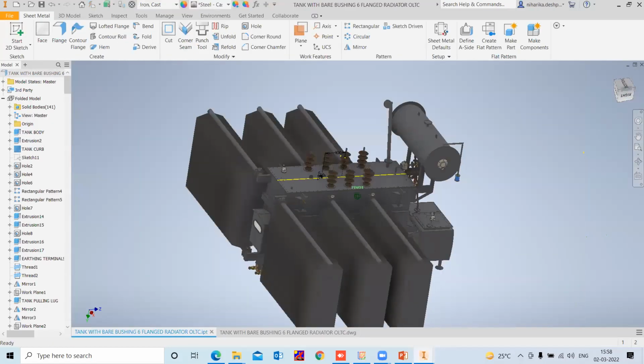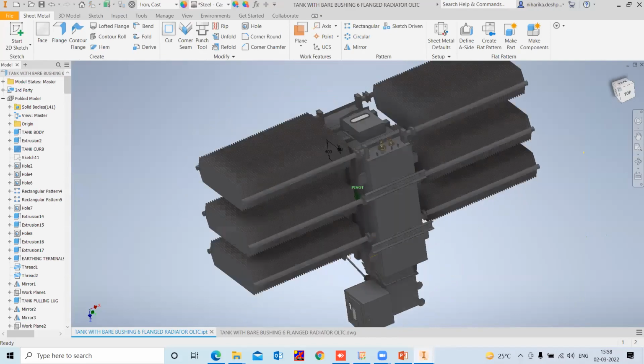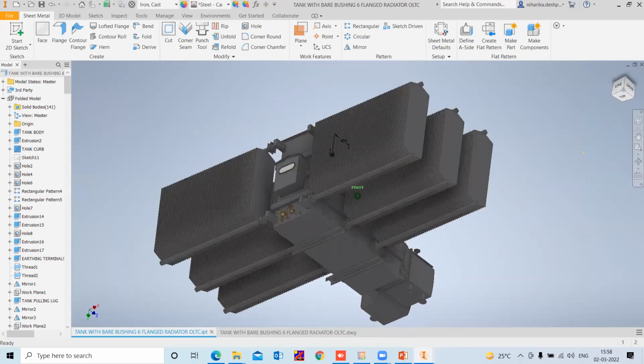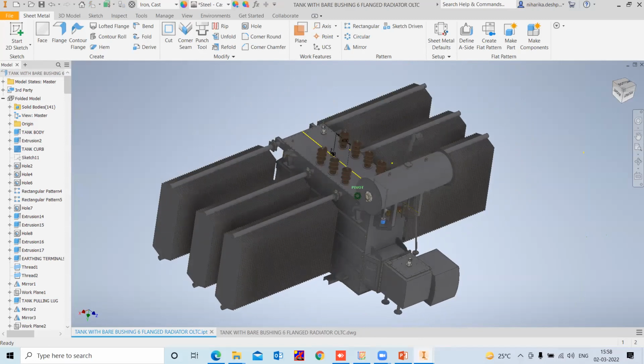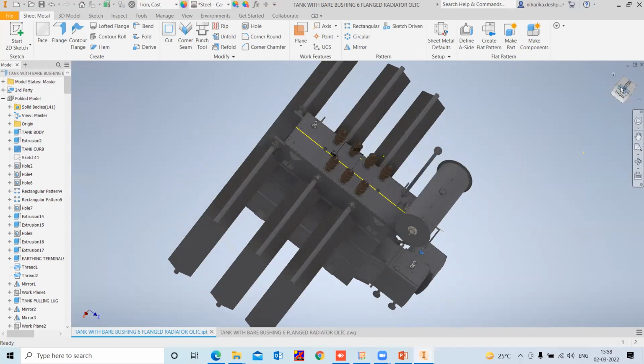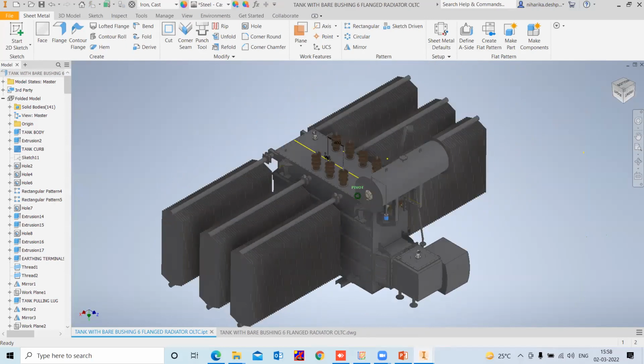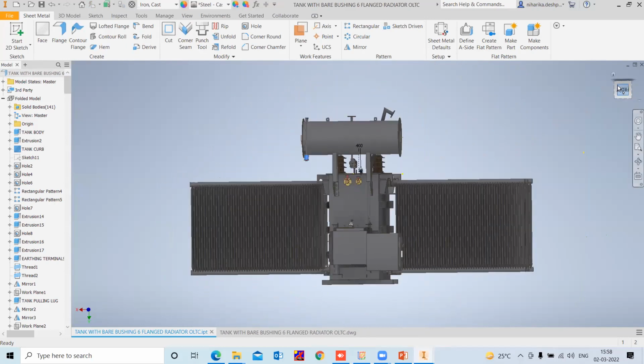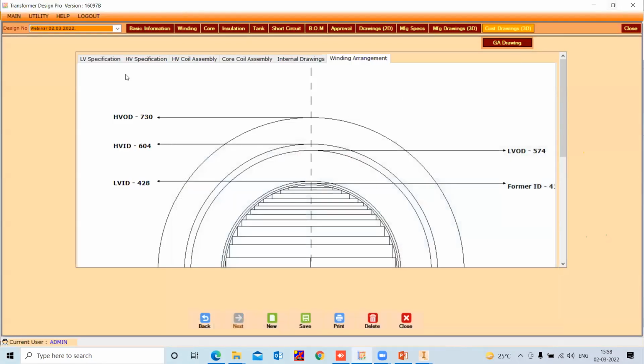And you can see this. If you want to increase the number of radiators, then the option is available on the tank page to provide pipes and make the maximum number of radiators if you have any limitations for width. But the software is taking care of the CG balance. It's simulating automatically. So this is all about the power transformer.